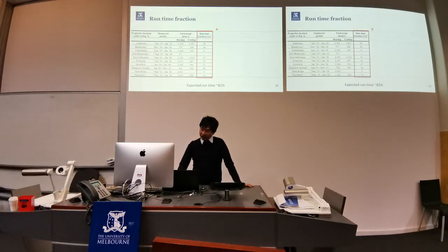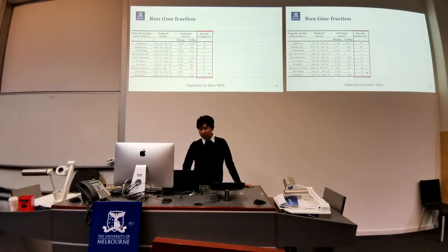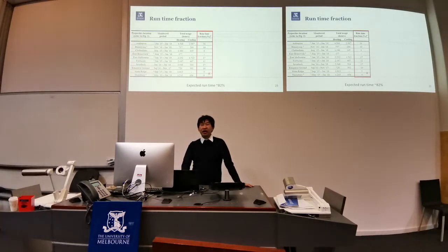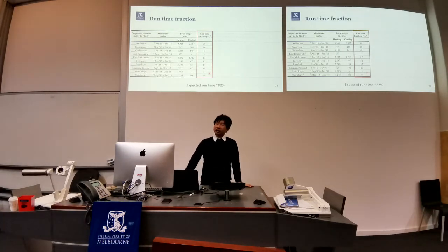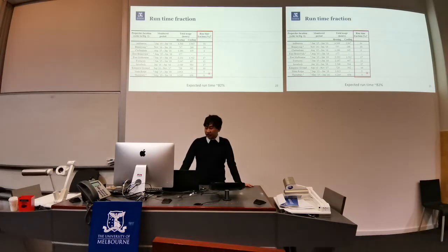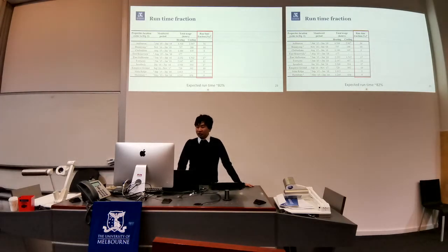It turns out that the low usage fraction applies to all the properties monitored here. As we can see from most of the properties we monitored, the run fraction was between 10 to 20%. A typical design method assumes that heating and cooling are required all year round, depending on the temperature outside the house, and assumes that the expected usage in Melbourne is about 80%. The temperate climate in Melbourne is actually mild enough, which results in minimum heating and cooling use throughout the year. Hence, for such a climate, the actual runtime of the system can be significantly lower than expected.